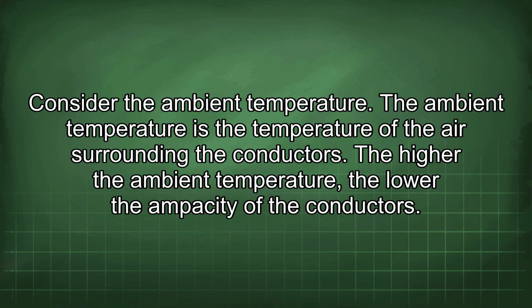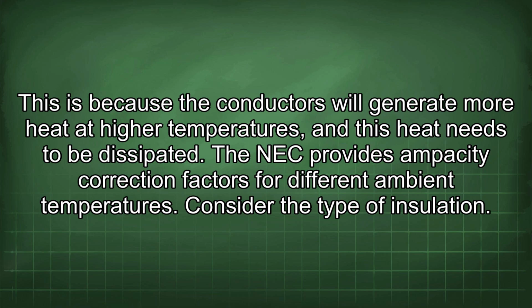The ambient temperature is the temperature of the air surrounding the conductors. The higher the ambient temperature, the lower the ampacity of the conductors. This is because the conductors will generate more heat at higher temperatures, and this heat needs to be dissipated. The NEC provides ampacity correction factors for different ambient temperatures.